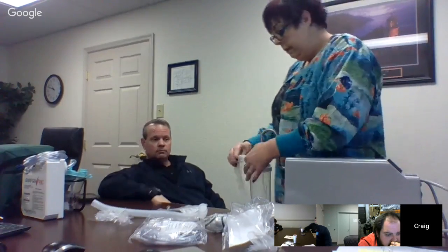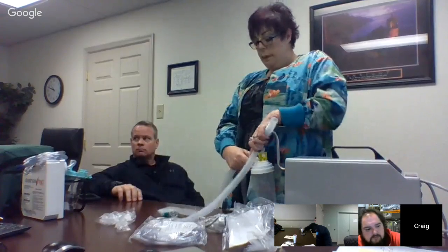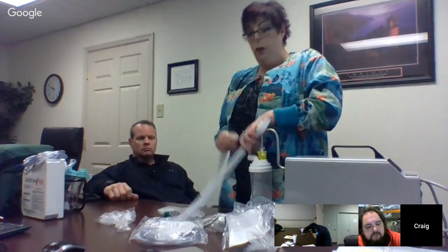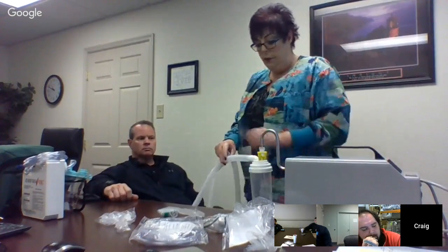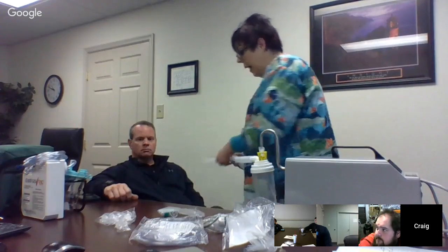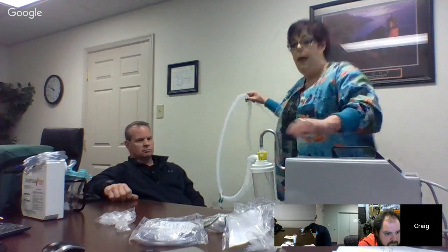Okay. So this tubing just hooks up to there. I'm going to use the shorter one so that the water trap's not so far up to the patient. And you kind of want to have it balanced, which my tubes are a little longer. That's only because we're trying to save money and I rigged something together. But you're going to want to put your water trap in line. And you always want your water trap to hang like this. Can you guys see that?